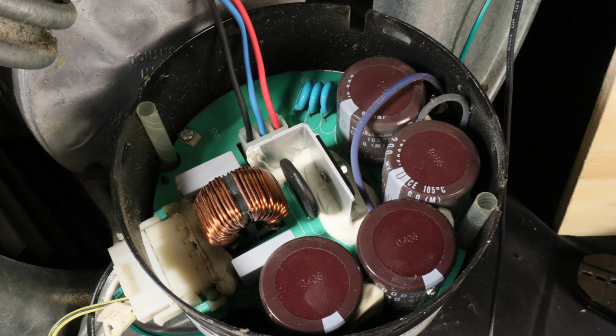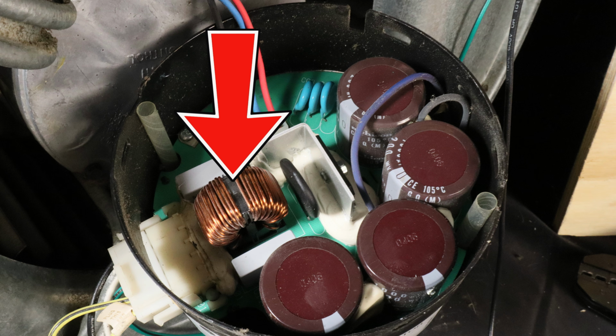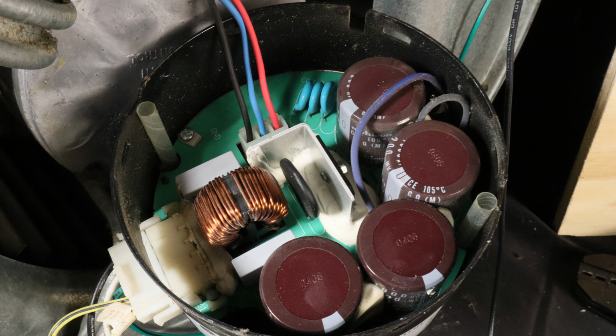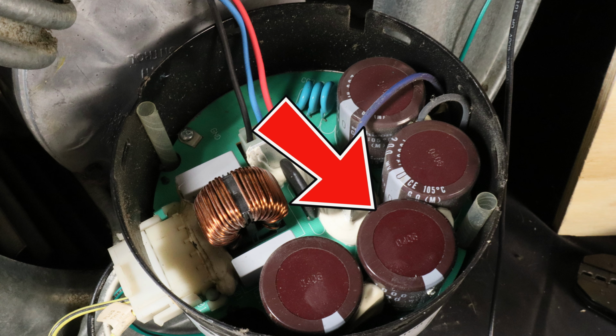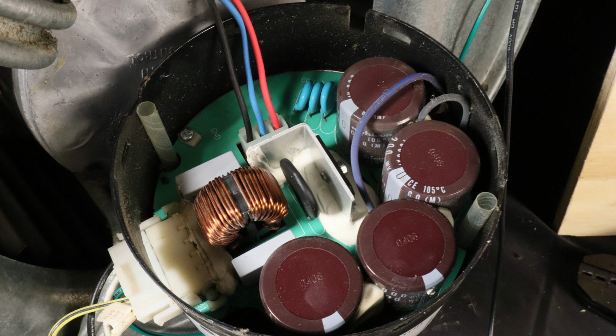And then it goes through this black core here with the windings on it, and that is a choke. It cleans up all the electrical noise on that signal. Then it goes through these brown cans here. That is our capacitor bank. And that takes that pulsating DC signal and turns it into a nice steady DC voltage. And then underneath all this, you can't see it, it turns that DC voltage back into 3 separate alternating current signals. So what we're doing here is we're simulating 3-phase power.